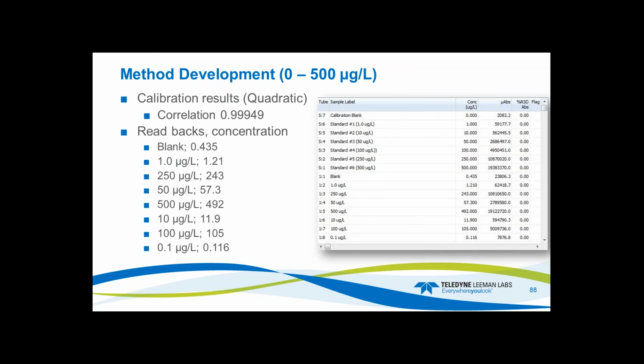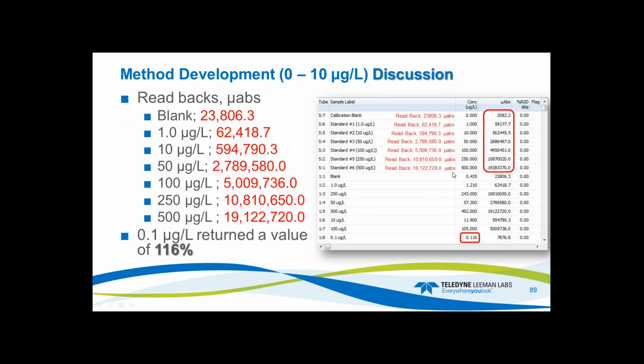So you can read lower levels, but I don't recommend it. And all the rest of it is almost right on. And if we look at our absorbance, now here we're in area, so that's why these numbers are so huge. But for example, 19 million, and you look over here, 19 million. At the 10, we're 594,000. Come over here at 10, we're 564,000. Now this is no big deal because look down here at the blank or the 0.1 at 0.116. My absorbance down here is 7,876. So small differences up here or large differences is not that really big of a deal.